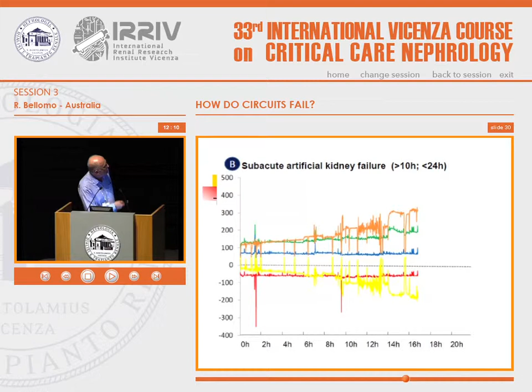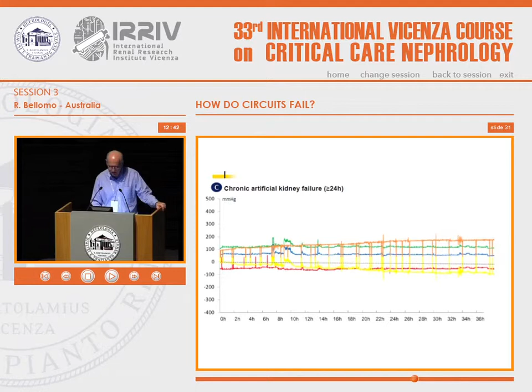Or you can be happy, or relatively happy, and again you see a progressive loss of filter membrane function, with the yellow bit being the effluent pressure, and a progressive application of negative pressure to this membrane, and a slow, steady increase in transmembrane pressure indicating progressive, slow coagulation of the membrane. You lose this filter at 36 hours instead of 10 hours.